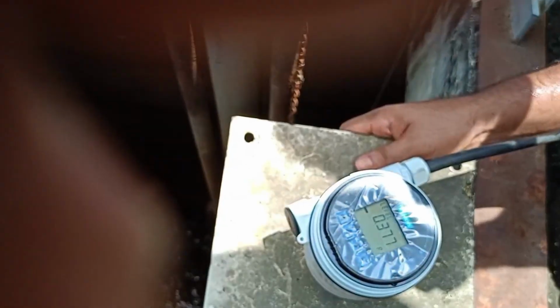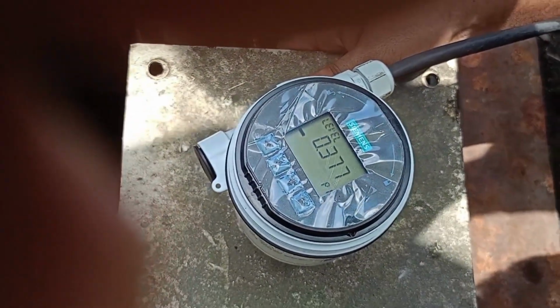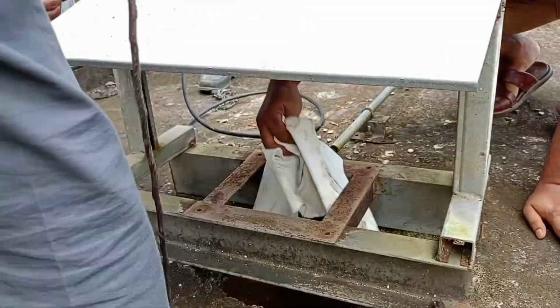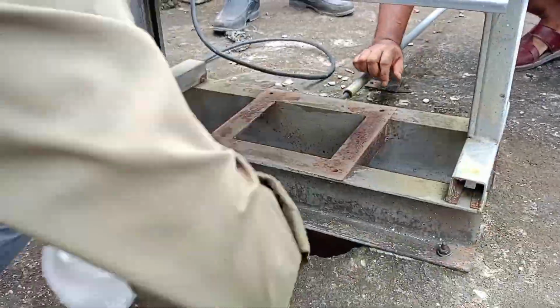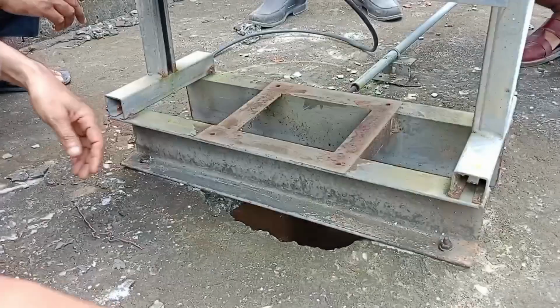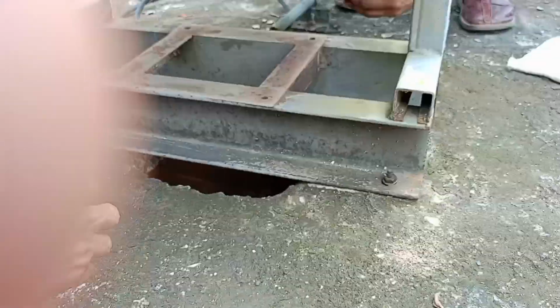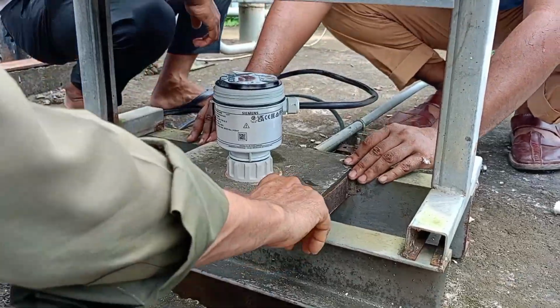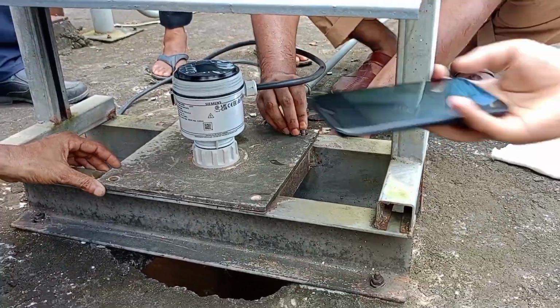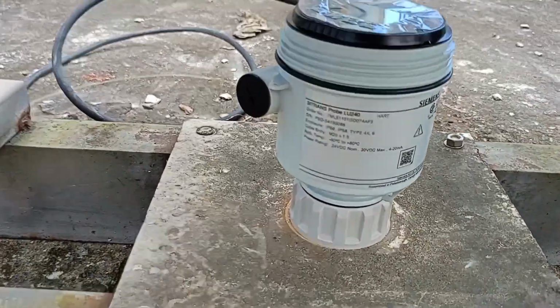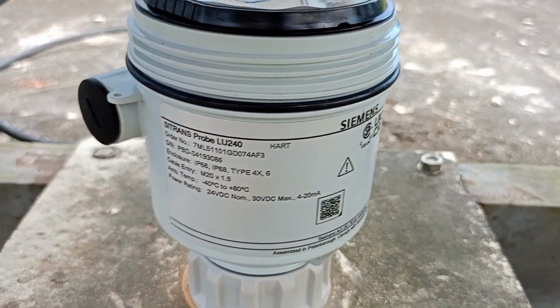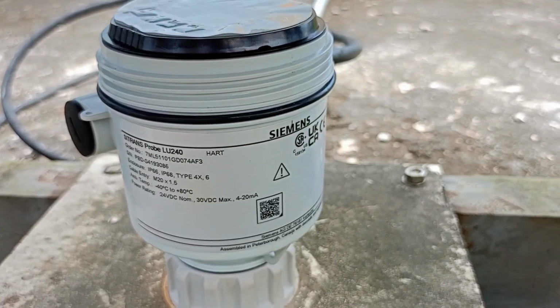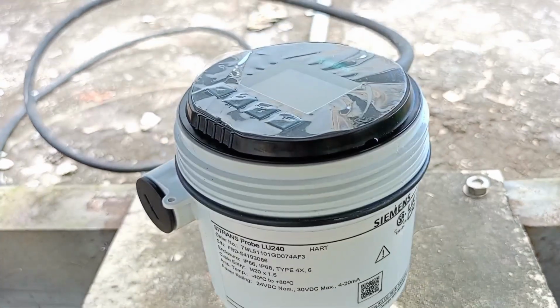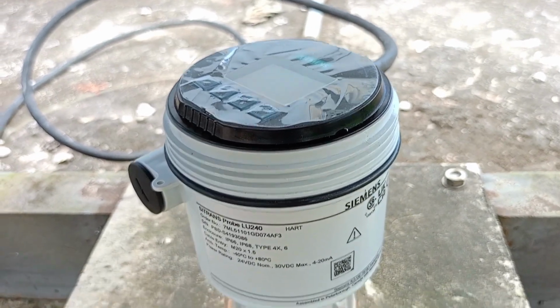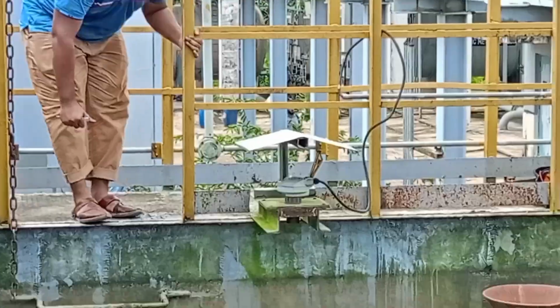After all completion of the work, we checked the reading from DCS. That means after increasing or decreasing the value, we followed the direct reading that we see from the DCS server unit, and the reading was okay. This is the newly installed transmitter which is installed on the base of the tank. You see, here is the unit that we installed, and we followed the reading.